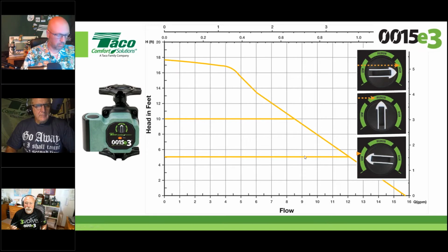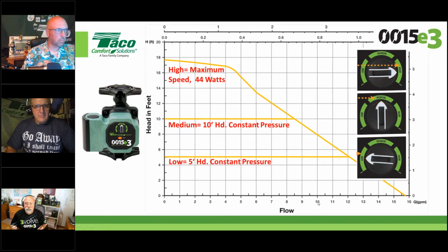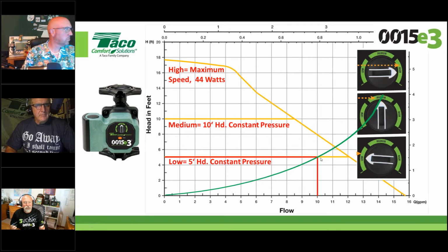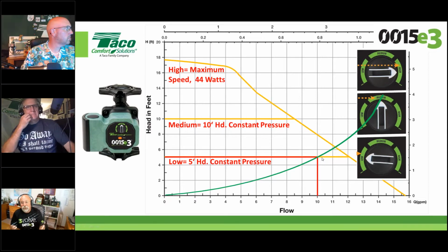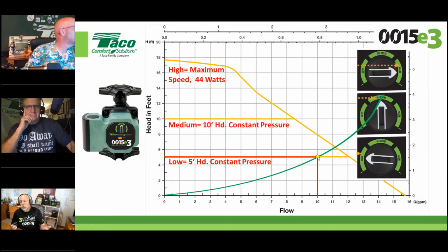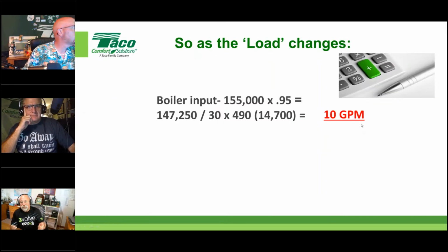Okay, and so let's see where that would do. Let's put the criteria in there at 10 gallons a minute and 5 foot of head, and we happen to fall right on one of the presets on constant pressure. Okay, just remember, constant pressure is an automatic mode, but it ain't ever gonna move automatically if you have nothing changing hydraulically downstream. And in this application, you wouldn't, so your operating point would be right there at 10 GPM and 5 foot of head. So there's the 10 GPM that we needed.